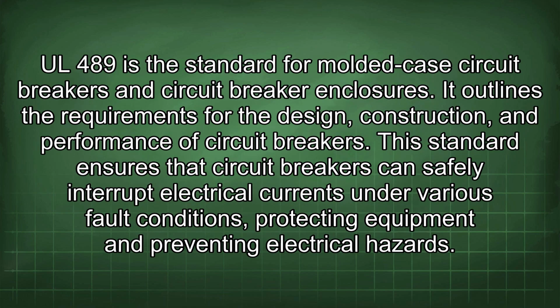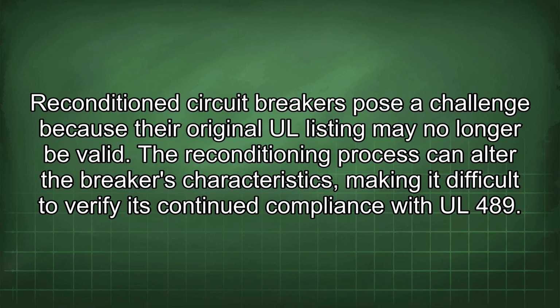UL 489 is the standard for molded case circuit breakers and circuit breaker enclosures. It outlines the requirements for the design, construction, and performance of circuit breakers. This standard ensures that circuit breakers can safely interrupt electrical currents under various fault conditions, protecting equipment and preventing electrical hazards. Reconditioned circuit breakers pose a challenge because their original UL listing may no longer be valid. The reconditioning process can alter the breaker's characteristics, making it difficult to verify its continued compliance with UL 489.